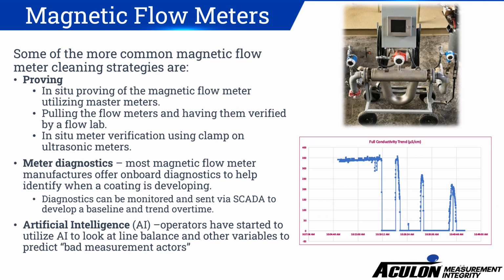Some of the more common strategies to determine when a magnetic flow meter needs cleaning are proving, meter diagnostics, and even artificial intelligence. There are several different types of proving methodologies. There's in situ or inline proving, where a master meter is utilized to determine the performance of the meter. You can see on the slide here a typical master meter configuration. You can also remove the meter, inspect it, have it tested at the lab or even on site, and then reinstalled. Another type is in situ meter verification using a clamp-on ultrasonic meter.